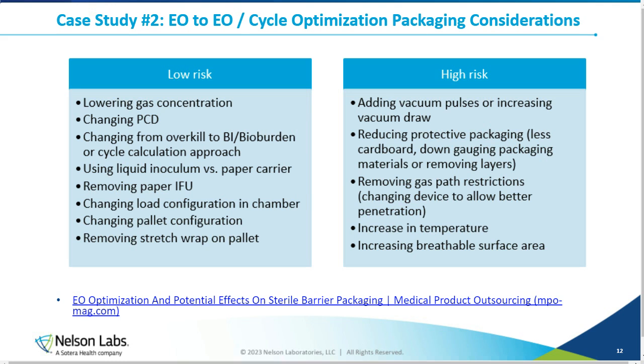The high risk column here, these are things that are most likely going to require you to do at least some supportive testing to show that whatever those changes are, they're not going to have a negative effect on the packaging system. The big one here is increasing the vacuum pulses or increasing the vacuum draw. That is going to put stress on the packaging seals, and there is a potential there that additional stress might cause a seal rupture that you hadn't seen before.